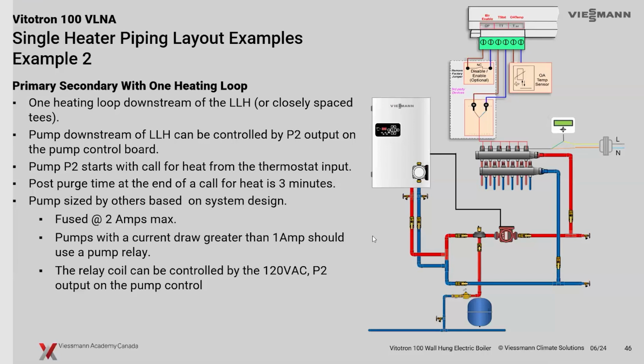Both those pumps will be enabled, and of course the boiler is going to energize the number of coils it needs based on the outdoor temperature. In this case, again, we have the outdoor sensor, and of course where our heating curve is sitting and what desired temperature we're going to be looking at that day as far as our requirements. Once the system is satisfied and opens up, there is a fixed delay of about 3 minutes on these little pumps before they'll shut off, after the call for heat is satisfied on that side.